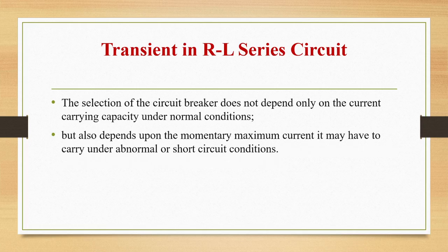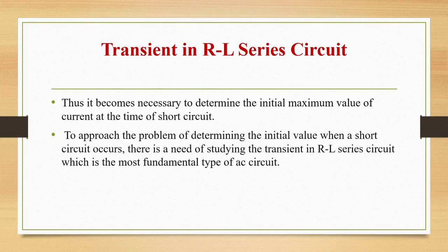So what we are telling here is that whenever we are selecting a circuit breaker, it should not be selected just by the current carrying capacity under normal condition, but it has to depend on the maximum current it may carry under abnormal or short circuit conditions. So it will become necessary to determine the initial maximum value of the current at the time of short circuit.